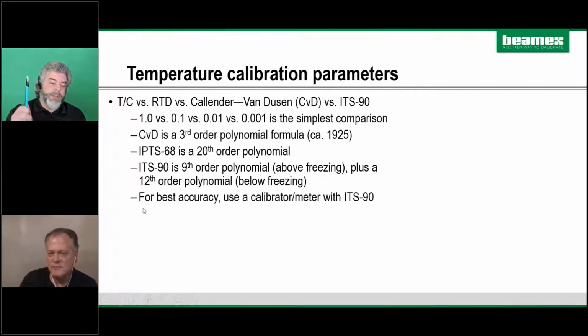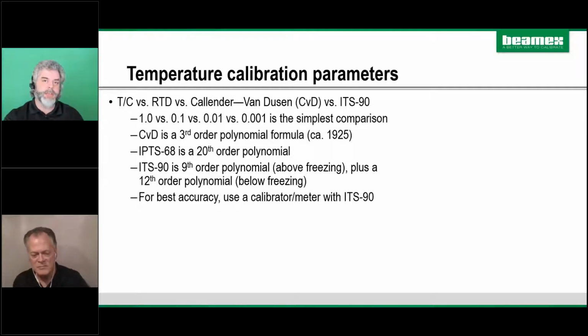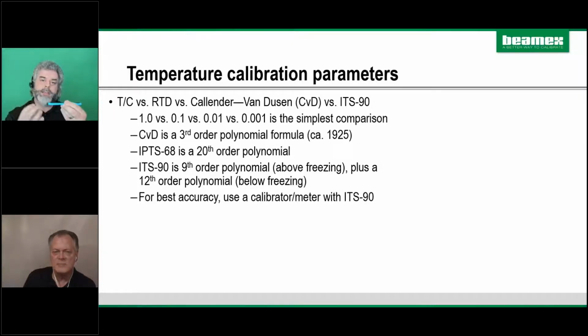As far as ITS-90 and Callendar van Dusen, it's an advance on a standard RTD curve. You'd think the temperature curve of an RTD would be perfectly linear, but it's not. The CVD and ITS-90 are characterizations that allow you to characterize that curve so where it's not exactly straight, maybe it dips down, and that's how you take advantage of these calculations to get it even more accurate. So this characterization is important.